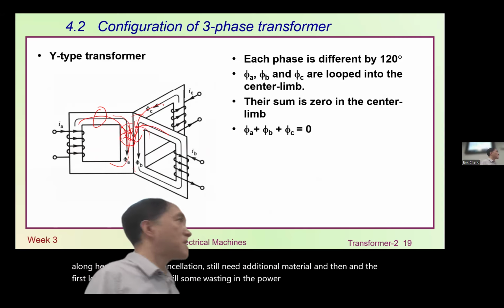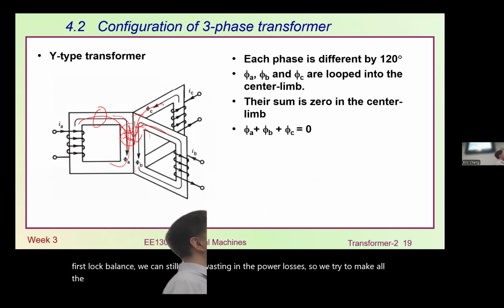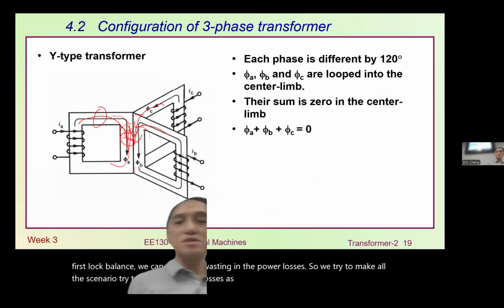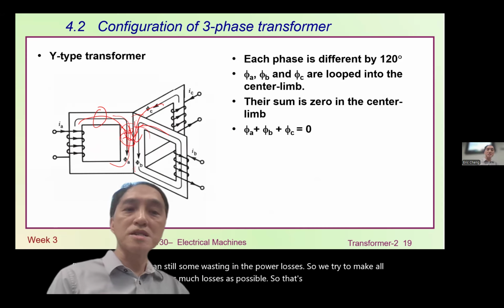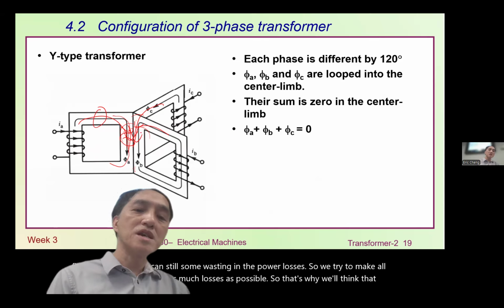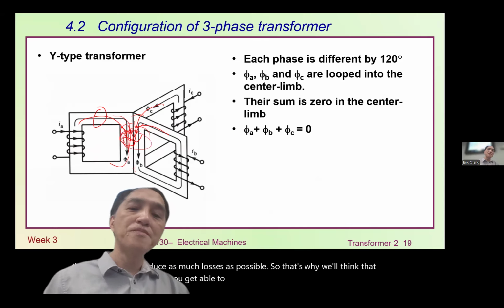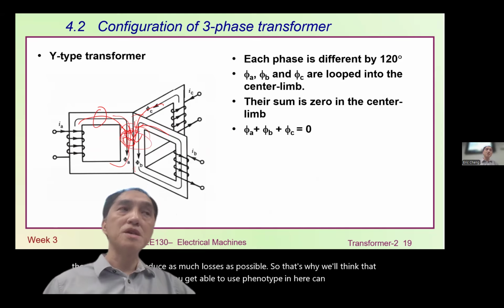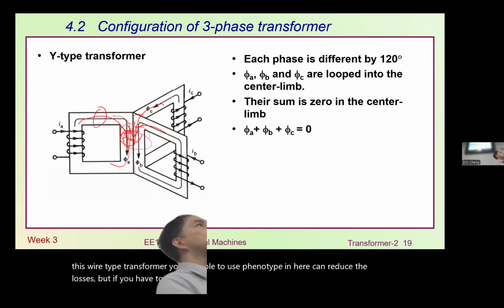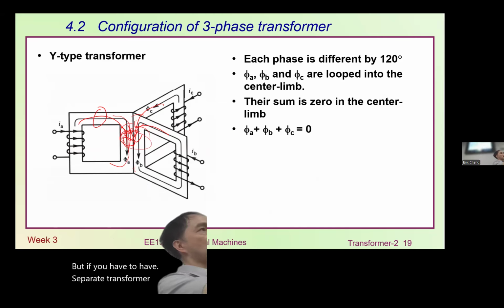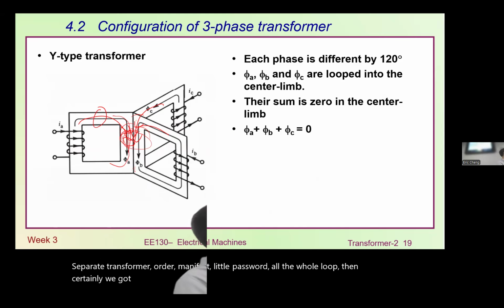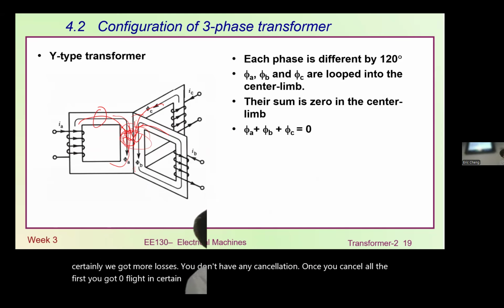So in every scenario we try to reduce losses as much as possible. That's why with this Y-type transformer we can use a thinner limb and reduce losses. But if you have 3 separate transformers, all the magnetic flux passes through the whole loop, so certainly we get more losses since there's no cancellation. Once you cancel all the flux and get zero flux in a certain location, you must have zero losses there.